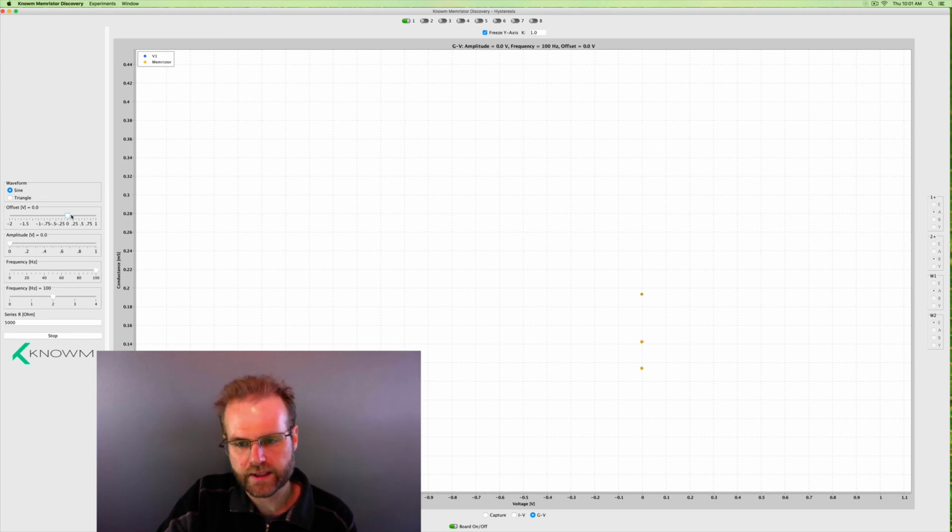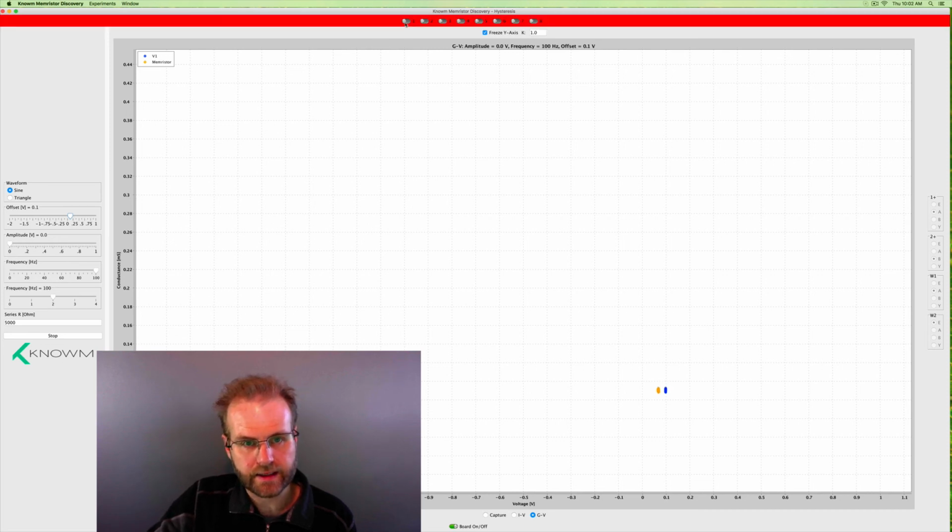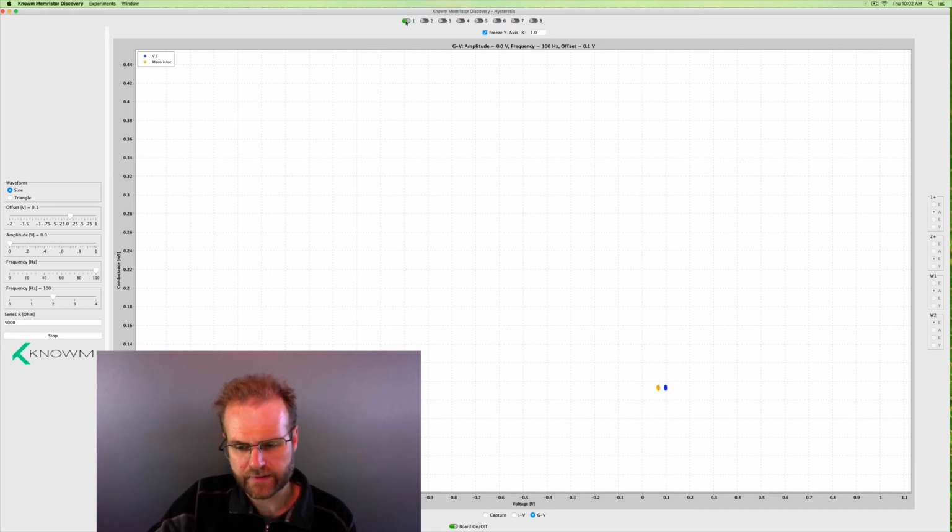Okay, so let's do one more cycle. Let's reset this. And we can drive it up one more time. Let's stop at, let's say, oh, that's good. Why not keep it low? Okay, so we are at 0.1 volts. We can deselect and select, see if we have a stable reading.